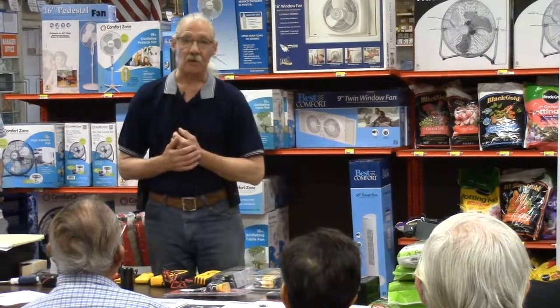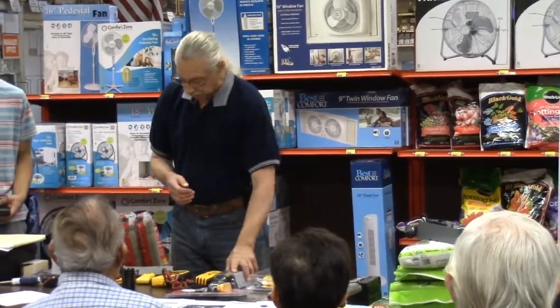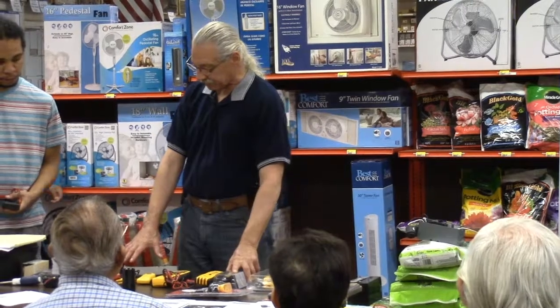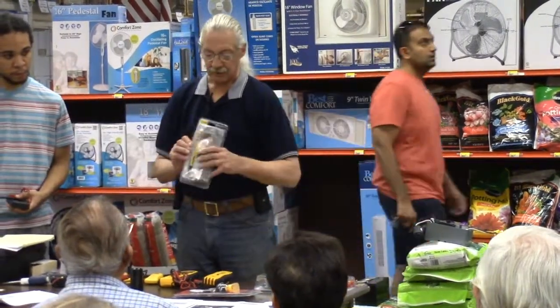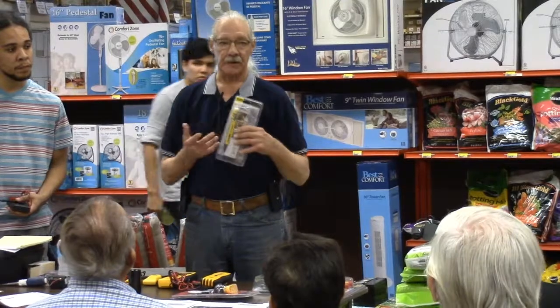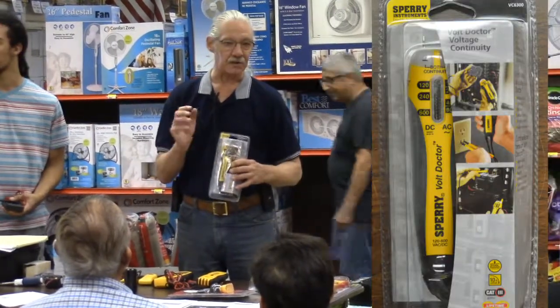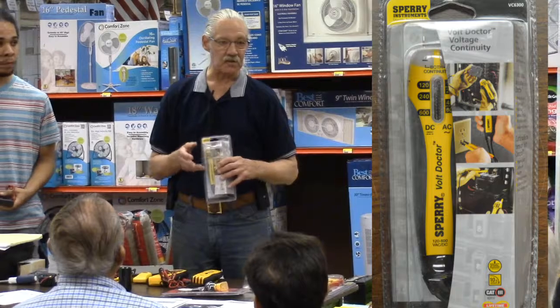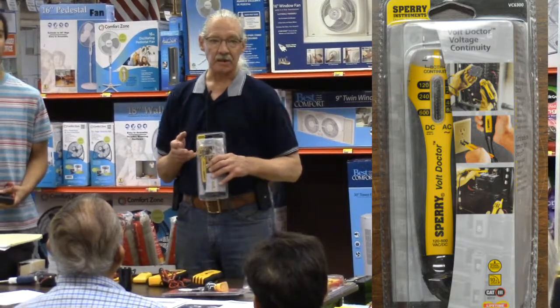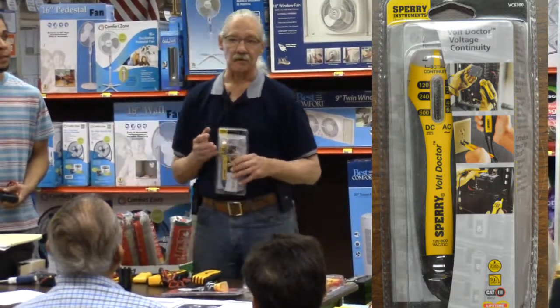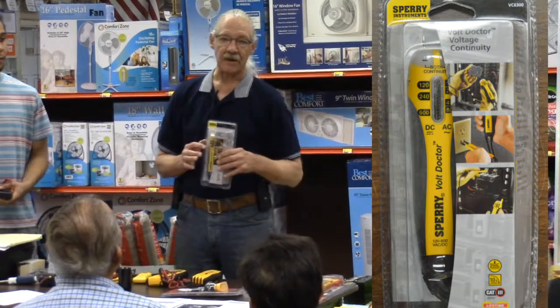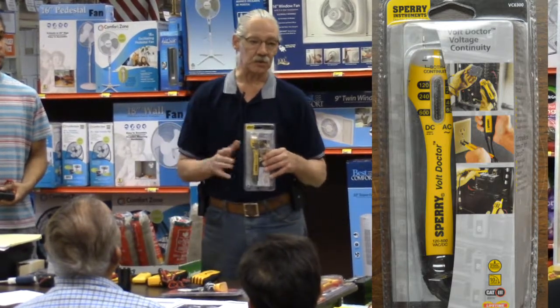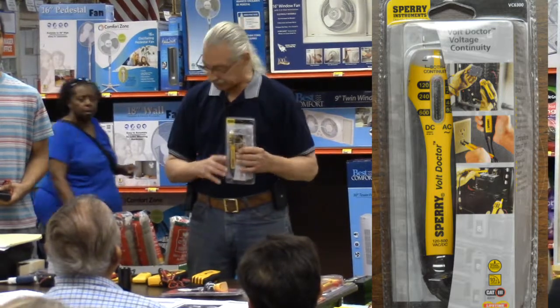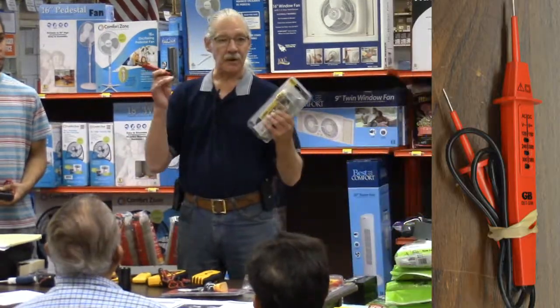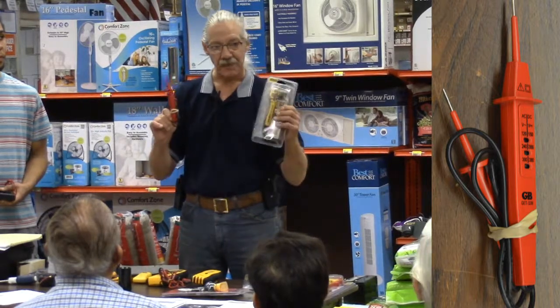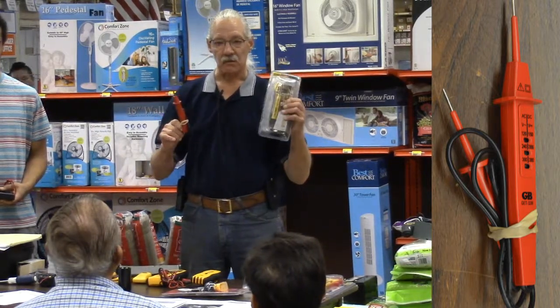A solenoid voltage tester - I'll show you a couple different testers - the solenoid voltage tester will actually buzz in your hand because there's an electric solenoid in here. That's there for a reason: it can't be activated by induced voltage. It's important on motors. So this is the top of the line compared to this one. They do the same thing, but this is a solenoid tester.